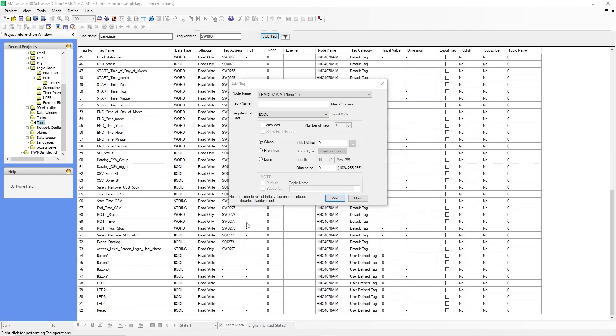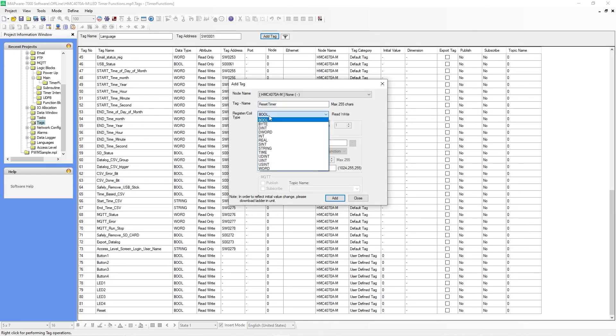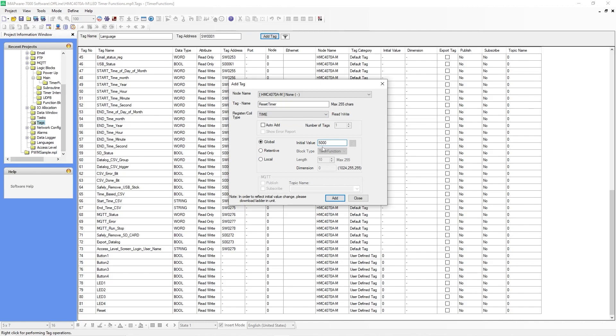The last tag I'm going to add is going to be a reset timer. Register type will be time, and for the initial value I'm going to enter 5000, which is 5000 milliseconds or 5 seconds. This tag is just for visualization — it's going to display a count from 0 to 5 seconds. This isn't a necessary tag; if I didn't add it, the timer would still count to 5 seconds. I will explain this a little later on. So just hit add.